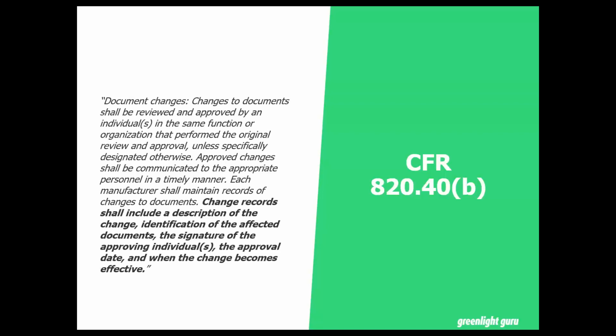Further, talking about changes, and specifically in this case document changes, if you refer to FDA 21 CFR 820.40, this is about documentation and record management. It gives some expectations with respect to changes to documents. So if you change a material, well, first and foremost, I would expect you to have some sort of material specification or some document or record that describes what that particular material is. You probably have a DMR, or you should have, you better have a DMR, device master record, that explains the materials, the components, the quantity, the size, the dimensions, all these things about your product as well. Well, if you're changing a material, something about your DMR is changing, something about your documentation is changing.